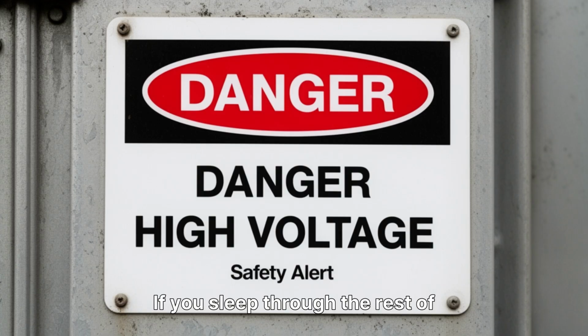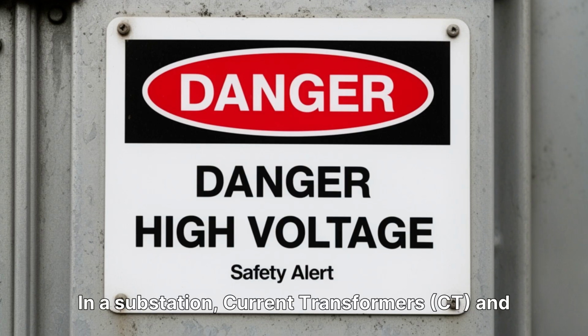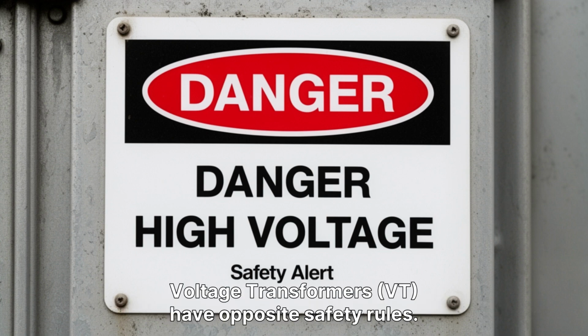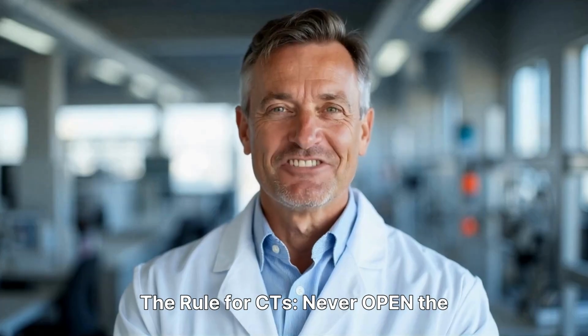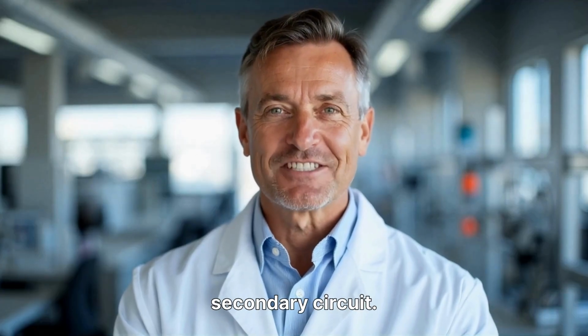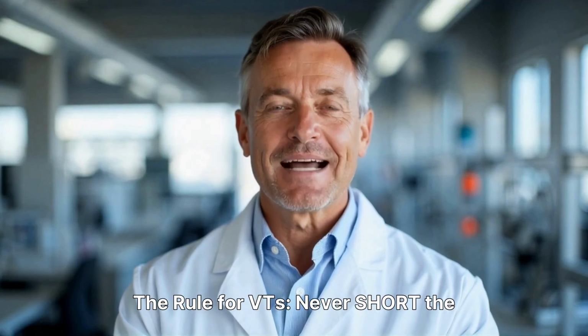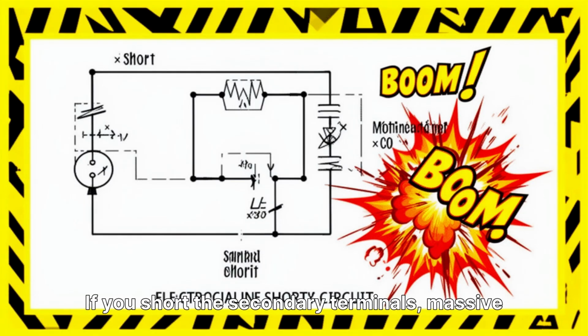If you sleep through the rest of this video, wake up now. This section saves lives. In a substation, current transformers, CT, and voltage transformers, VT, have opposite safety rules. The rule for CTs, never open the secondary circuit. The rule for VTs, never short the secondary circuit. A VT is a voltage source. If you short the secondary terminals, massive current will flow, melting the windings in seconds. That's why you always see fuses or MCBs on the secondary side of a VT.